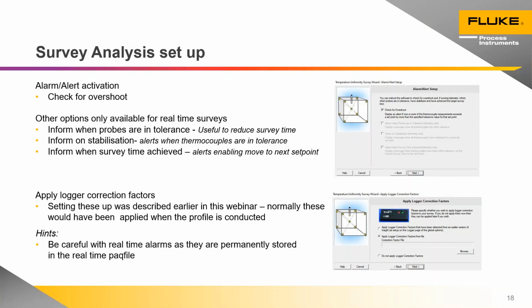You can see there's a number of options that are grayed out here. These would be alarms or alerts that you would actually use when conducting a real-time survey, and these would be able to alert the user when those stabilization criteria that we talked about on the previous slide have been met, enabling you to go from one set point to the next very quickly, or in fact in the shortest possible time, so saving time on surveys.